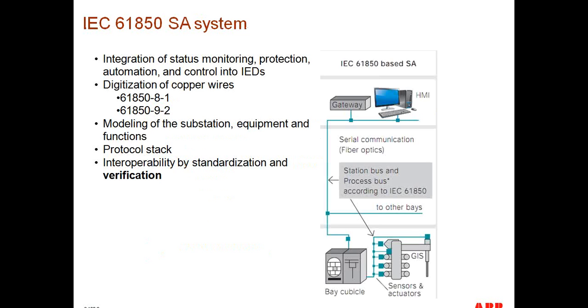So, as discussed in the previous webinar, this is an IEC 61850 based substation automation system. The assumption here is that we have our primary apparatus, our substation breakers, and by utilizing a communications network, the status points from the power system are being transmitted up to an HMI/gateway. And this bus right here, this line, is really just a representation of a communications network in the form of an Ethernet network.